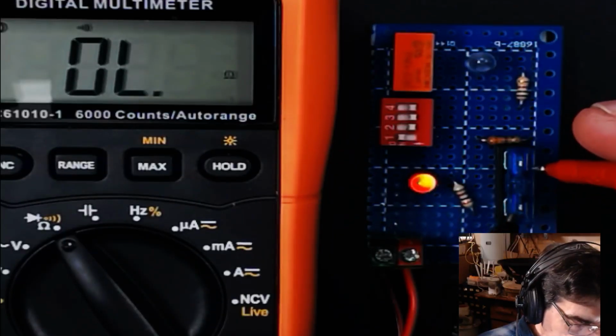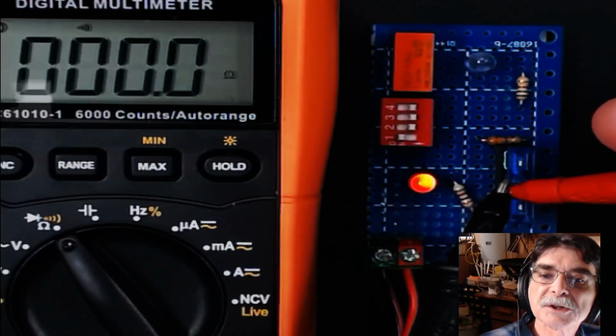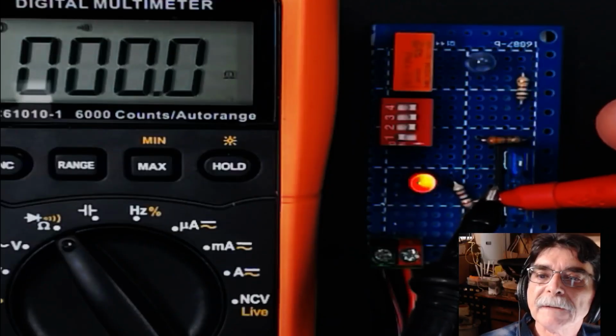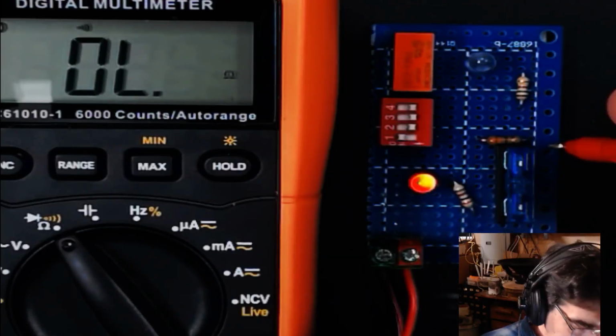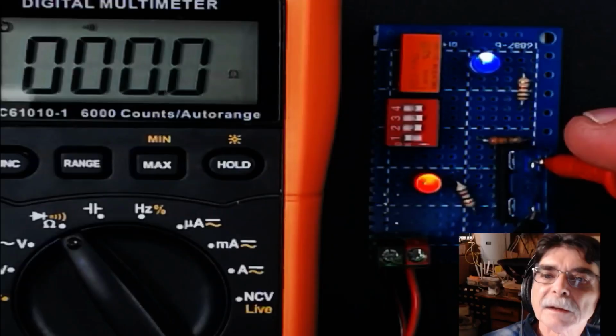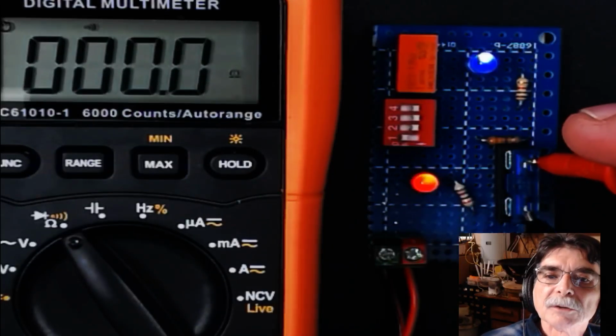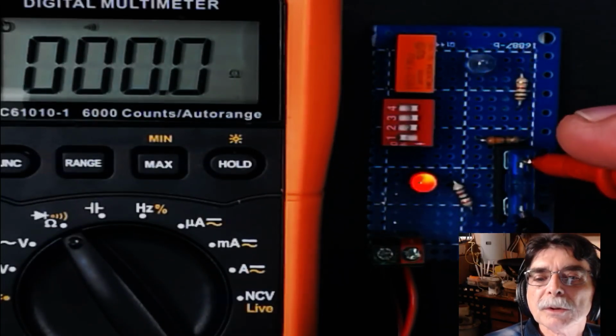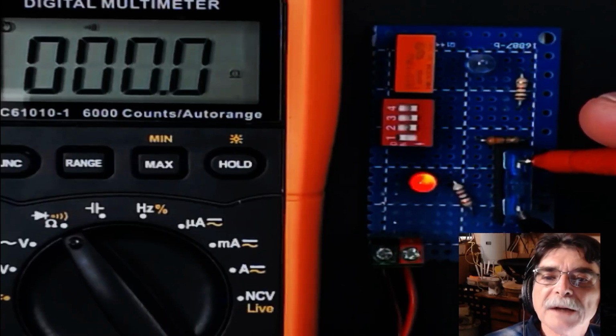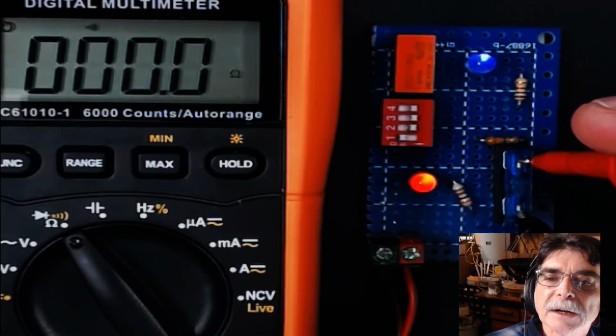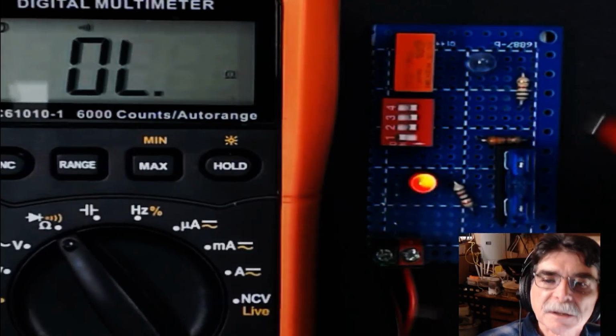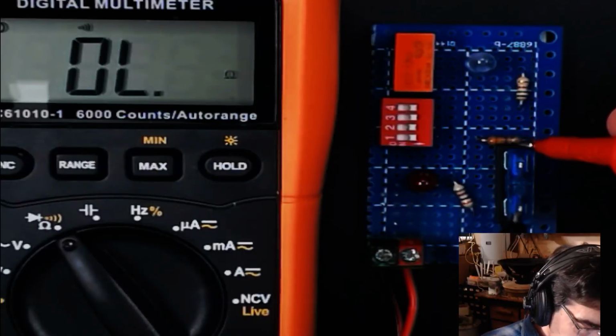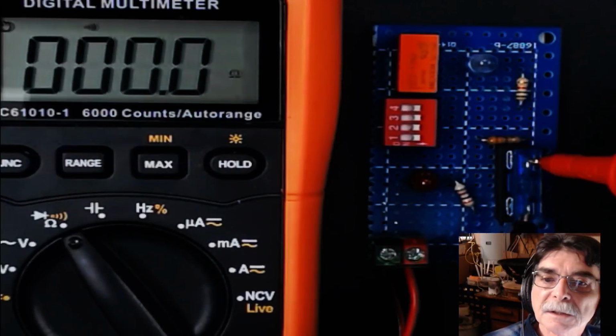But watch what happens with continuity. We're going to touch the probes together. It shows it's a short. You might be able to hear it beeping. Watch this. It shows a short. So in other words, if you were to measure this fuse with continuity, you would go, oh, I got a good fuse. I got continuity. So why is this happening? And even if the LED is off, we still get continuity in an energized circuit.